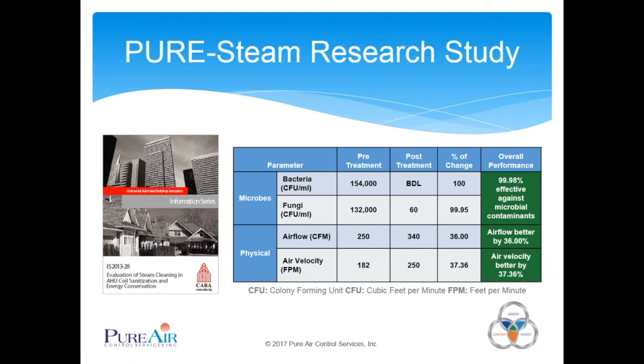So before PURE-Steam, from the data collected and tested and analyzed by our environmental diagnostics laboratory, it was found that there were 154,000 bacteria colony-forming units per milliliter in these coils, and after PURE-Steam, it was below detectable level. There was nothing even being detected. It was a 100% improvement with regards to bacteria. Now, fungi is a little bit different story, but still quite excellent, because that dropped down to only being able to detect 60 colony-forming units per milliliter, for a 99.95% change. So with CABA reporting and backing up our findings, we're seeing that PURE-Steam is basically 99.98% effective against microbial contaminants that are growing on the coils and inside of the air handler unit.